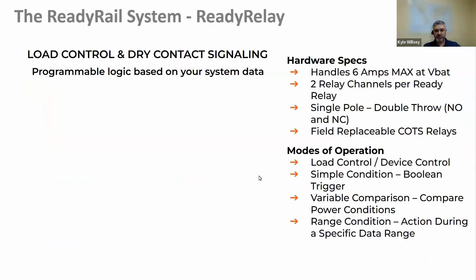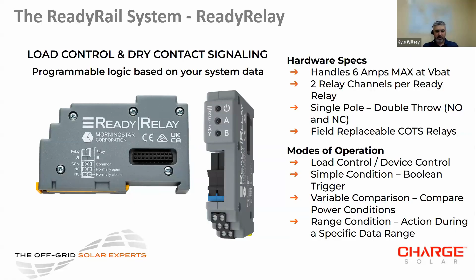Here's a deeper look at that Ready Relay. It's two relay channels, dry contacts. It handles up to 6 amps itself, but could also be used to drive a larger relay if that's not enough power. It can be used as a simple on-off, like in a load shedding scheme, kind of an LVD mode, or you can build more complex Boolean logic triggers, for example, if the solar array is not producing an average amount of power, shed some loads that may not be so critical. There's a lot of I/O, configurability, and control you can do with this product.